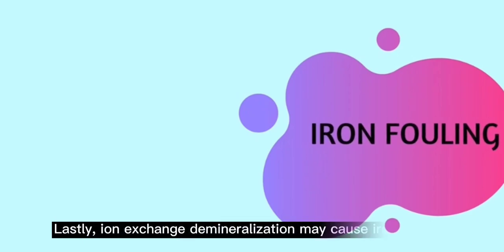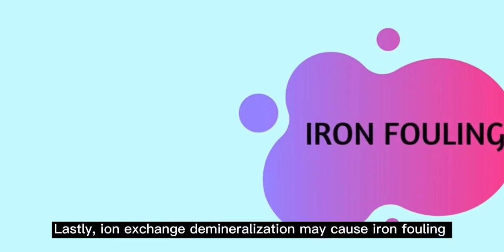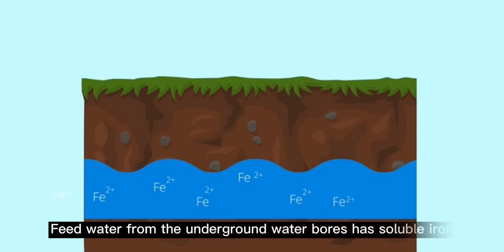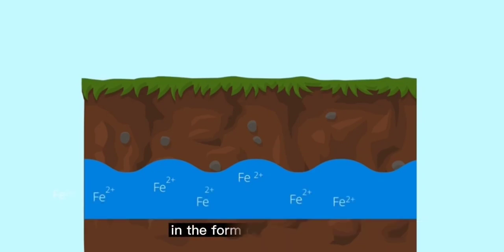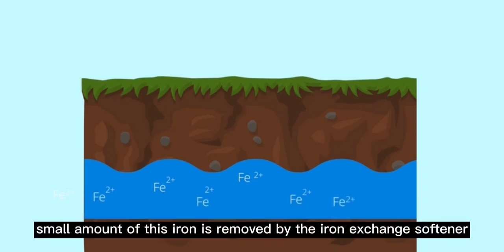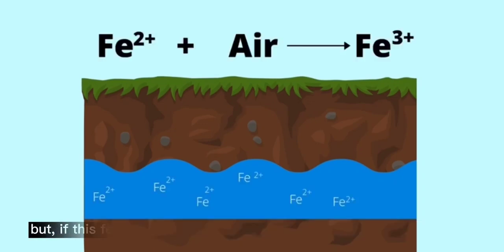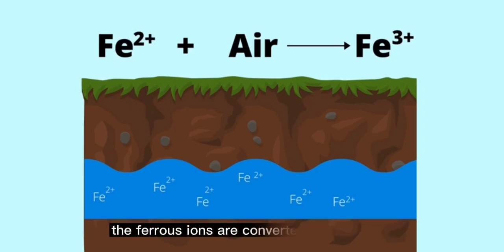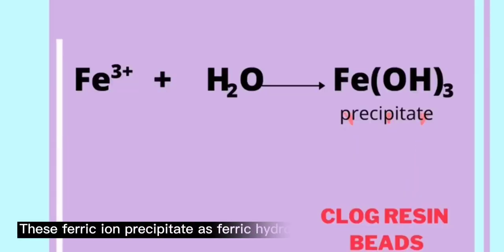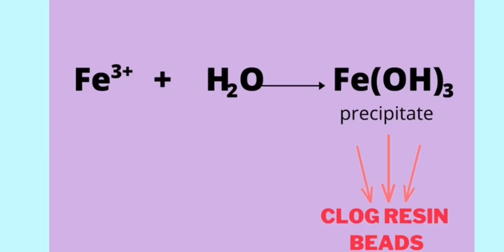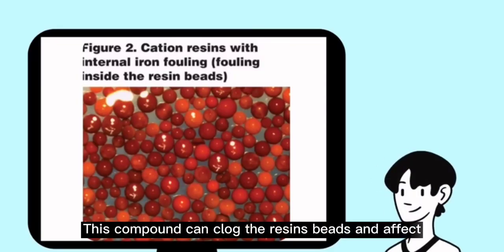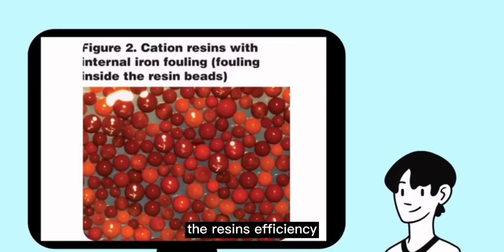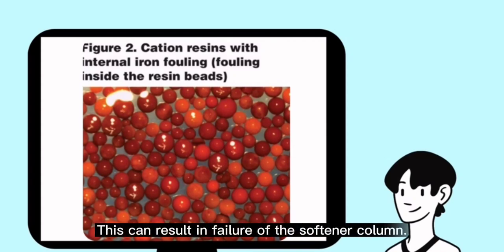Lastly, ion exchange demineralization may cause iron fouling. Feed water from underground water bores has soluble iron in the form of ferrous iron. Small amounts of this iron are removed by the ion exchange softener. But if this feed water comes in contact with air before treatment, the ferrous ions are converted to ferric ions. This ferric ion precipitates as ferric hydroxide after reacting with water. This compound can clog the resin beads and affect the resin efficiency. This can even result in failure of the softener column.